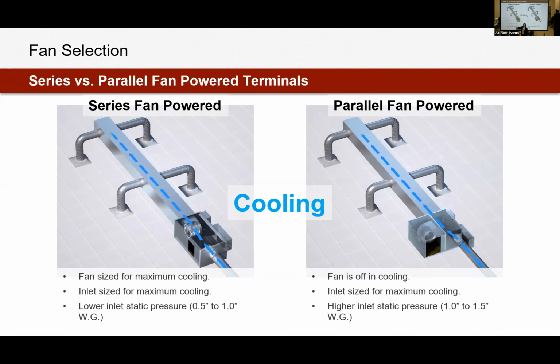That is very important. In your parallel box, our inlet valve and our fan are in parallel with one another. They're not in line. If we were to chop off this fan side of the box, it operates just like a single duct. It looks like a single duct. So they are kind of two separate components coming together side by side, just like a circuit.